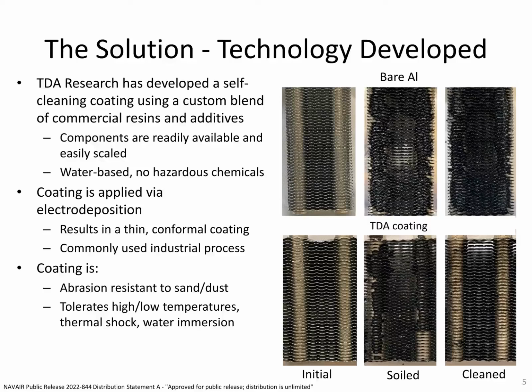We've also tested the effects of the coating on heat transfer and seen that a coating thickness of up to 1 mil will not decrease heat exchanger efficiency. Most importantly, we've shown that our coating reduces heat exchanger fouling by 50% compared to an uncoated aluminum heat exchanger.